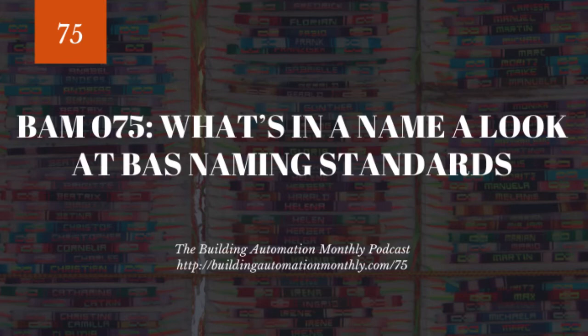Well, from my experience, there's really three things that make a good naming standard. The first is that the naming standard is clear. You want to be able to look at a standard and immediately tell what it's referring to. So let's say you have a college campus, and this campus has a building called Waters Building. Waters Building has three floors, multiple different rooms, and it has fan power boxes or fan coils. So what you might do is Waters Building dash Floor 1 dash Room 101 dash VAV.